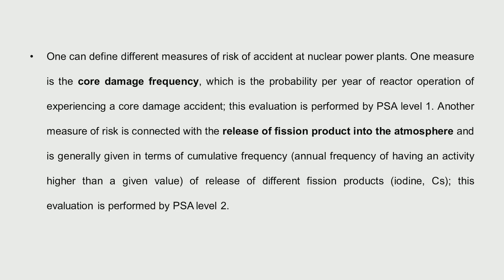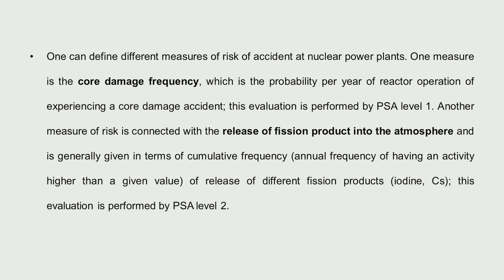Coming to nuclear reactors, which our whole subject of talks in these lectures is about — what is the risk of damaging the core? If the core is damaged, the fission products from all the fissions which have already occurred will come out. So we measure the core damage frequency: the probability per reactor year of experiencing a core damage accident. In the terminology of probabilistic safety analysis, this is called Level 1, which is the most important — what is the frequency with which core damage can happen?